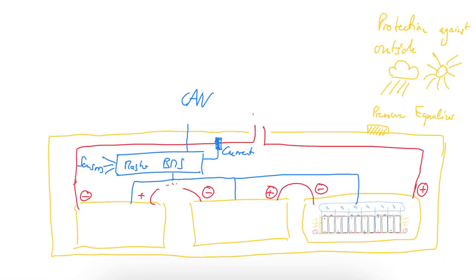What else is missing is the connection to the outside. Like you have then the modules connected. You have typically short cables that go then from the end of the module, from the kind of final poles to the connection. And one thing that is in between is normally a switch because I think I said it already, I'm pretty sure I said it already, you can't switch off a battery. The chemistry is always working but nevertheless you want to make sure that the battery case, the battery as itself can be saved by switching off the contactors so that there is no voltage, no live part basically exposed.